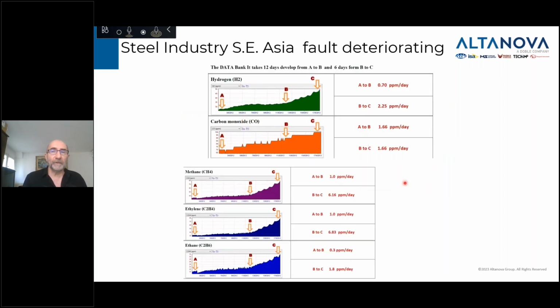First, because the system shows you a change in the behavior of the fault. If you look at it from time A to time B, the rate of generation of those gases was pretty low. But then, in a much shorter period of time, nearly half the time period between A and B, the rate of generation of those gases has increased by a factor of 4 for the hydrogen, and by a factor of 6 for mostly all the other key fault gases, methane, ethylene, and ethane. So what this tells you right there is that you have a fault. The fault is deteriorating, is getting worse, and the temperature of that fault is also increasing.